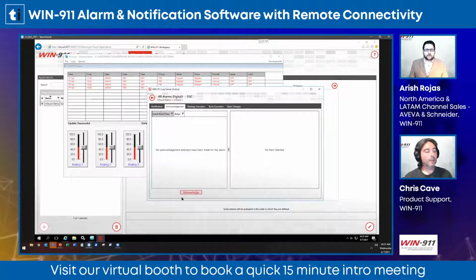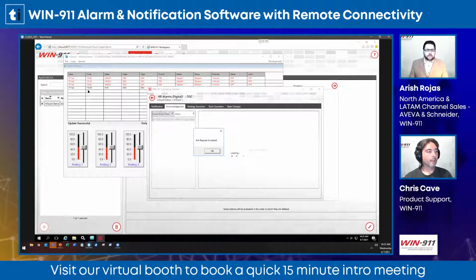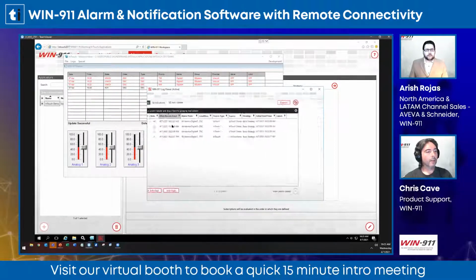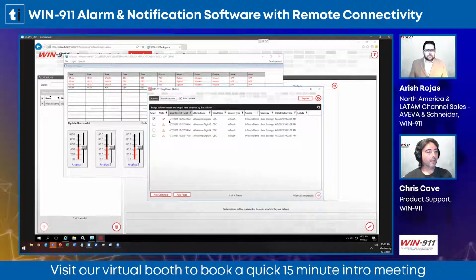From here, we can actually acknowledge the alarm if we want, back to the SCADA. Here we can see that it updated my SCADA alarm summary screen. We hit the red arrow to get back, and now we can see that we have one alarm acknowledged.